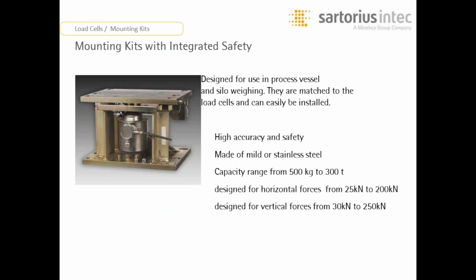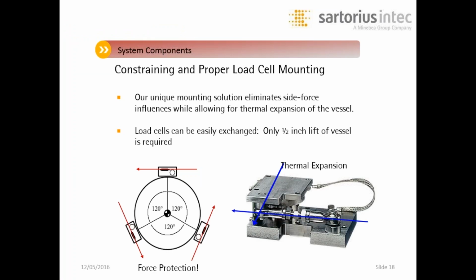Okay. Mounting kits, when choosing for a tank assembly, must be designed for use in process vessel and silo weighing. That's what the canister load cell mount that you see before you today has been designed for. They're highly accurate, made of mild or stainless steel. They have huge capacity ranges from 500 kilograms up to 300 tons, designed for horizontal forces from 25 kilonewtons up to 200 kilonewtons, and vertical forces from 30 kilonewtons to 250 kilonewtons.